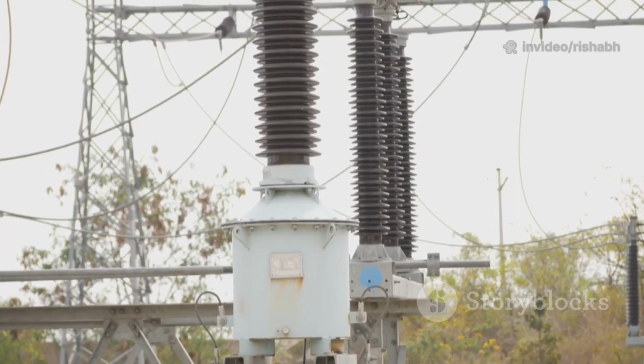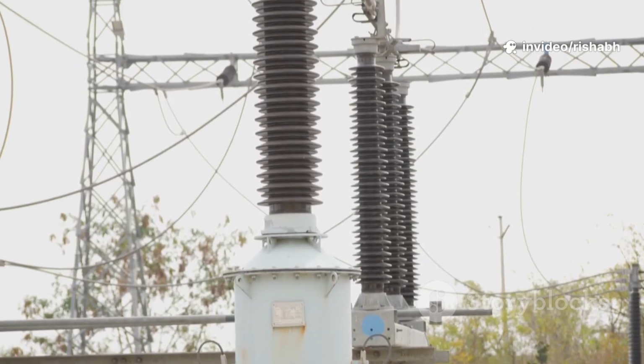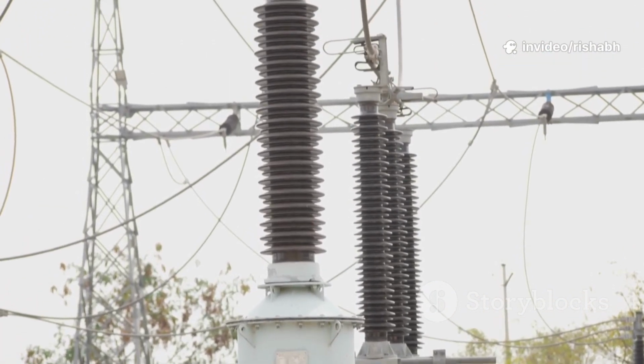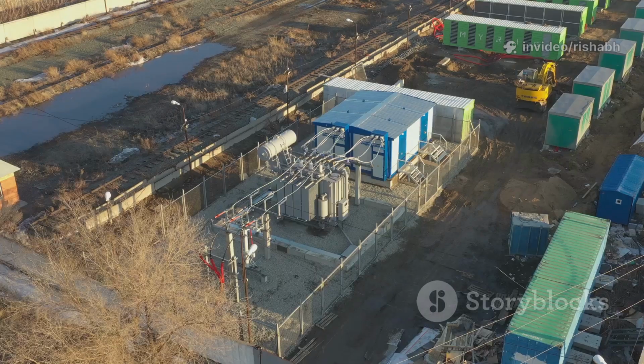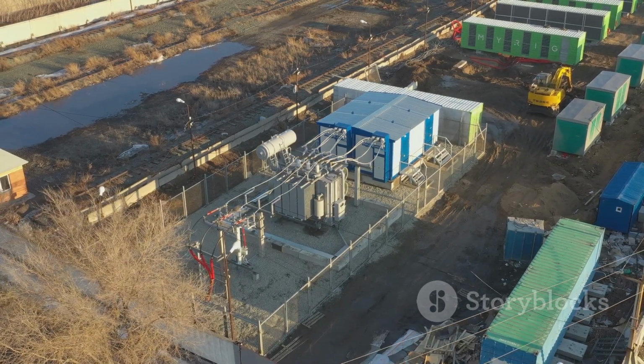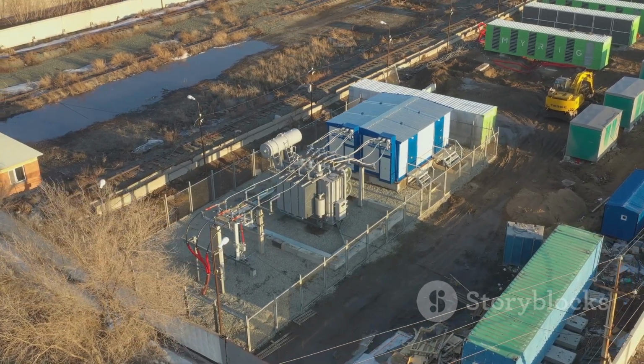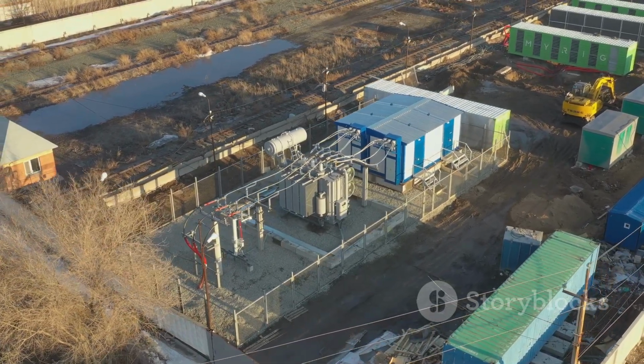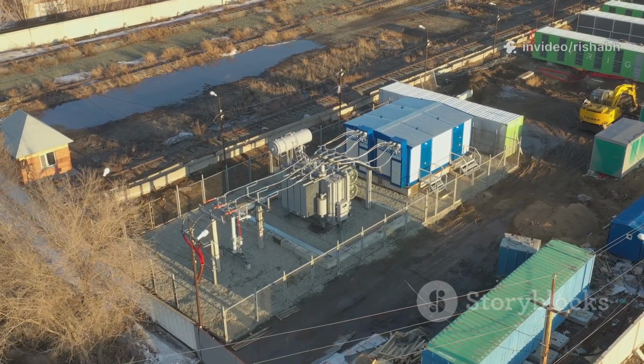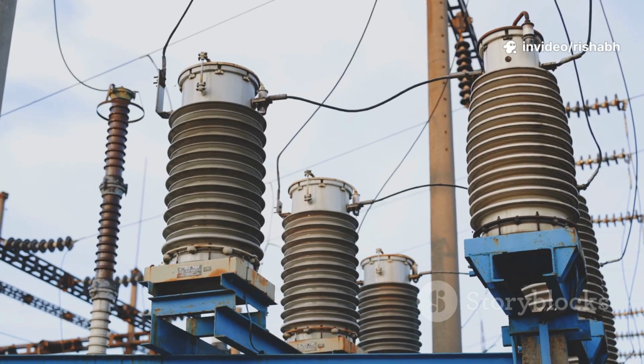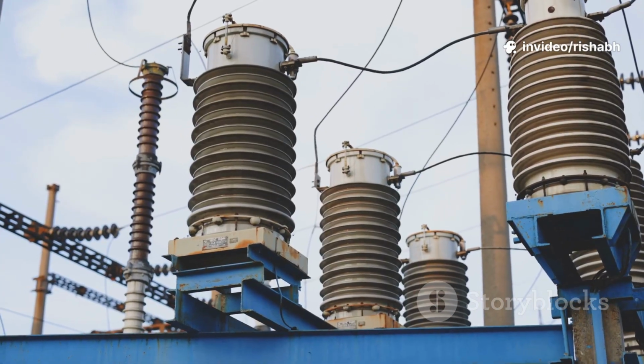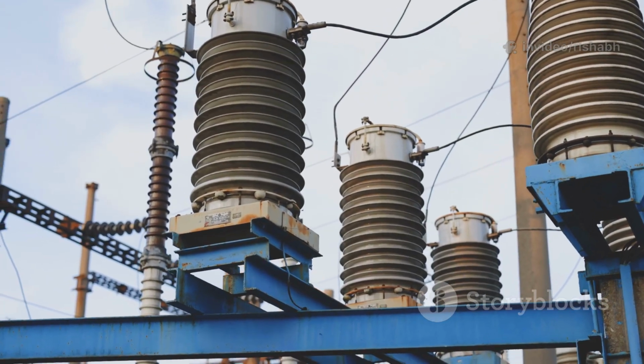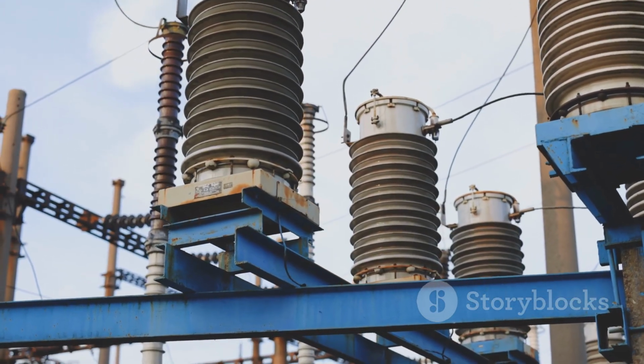This combination of oil and cellulose actually has a much higher dielectric strength than either material alone. It fills all the gaps, preventing electrical discharges from initiating and creating a robust barrier against the immense voltage. It is the fluid medium that isolates the high-voltage components, allowing them to operate in close proximity without arcing over.